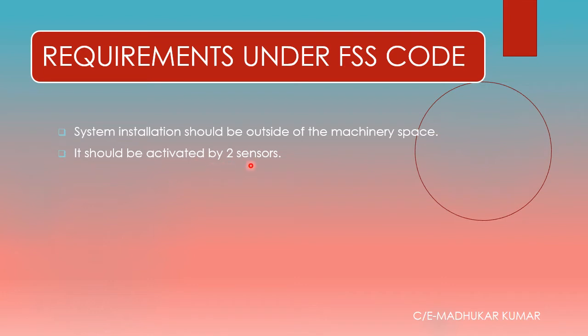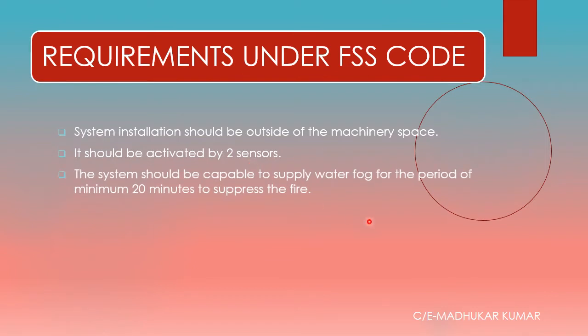The system should be activated by two sensors — a flame sensor and a smoke sensor. Both sensors must be activated together to trigger the hypermist system in that particular zone. The system should be capable of supplying water fog for a minimum period of 20 minutes to suppress the fire.